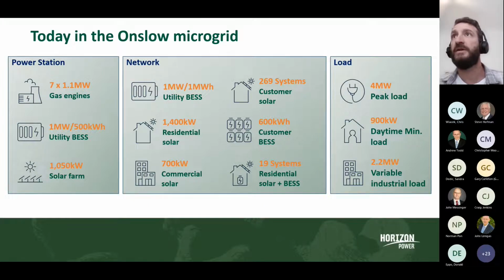It's a small microgrid, around 4 megawatts peak load, with a minimum daytime load of about 900 kilowatts. So with 3 megawatts of solar during the day against a minimum daytime load of around 900 kilowatts, there's a significant imbalance we need to manage. On top of that, we have a highly variable industrial load of about 2.2 megawatts coming in and out as it will.